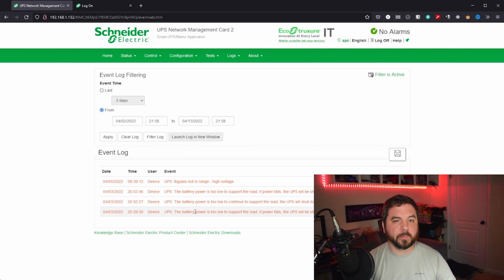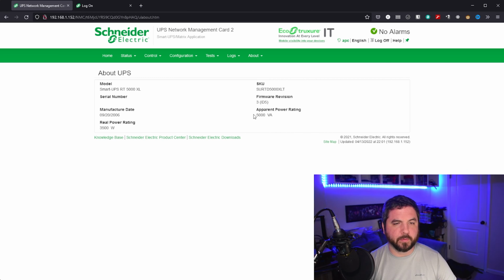And let's see. So this is the about page. This is the model number, the SKU. The manufacture date was 2006. Pretty old at this point. The volt amps, 5,000 and 3,500 watts. You need to make sure that when you're sizing out your UPS that you don't go too crazy. I mean, they do make these up like 8,000 or even higher volt amps. You just have to make sure you have the proper sizing.